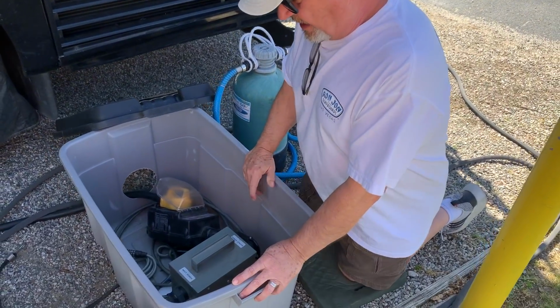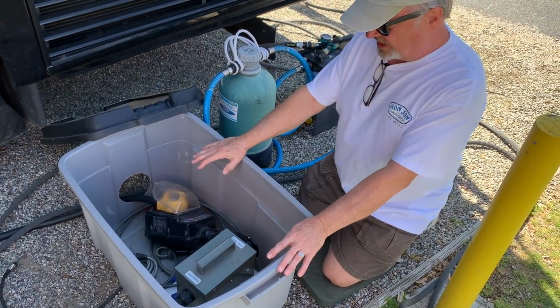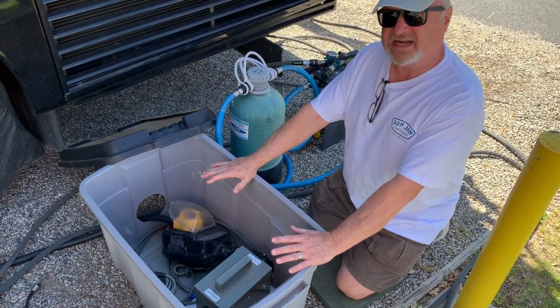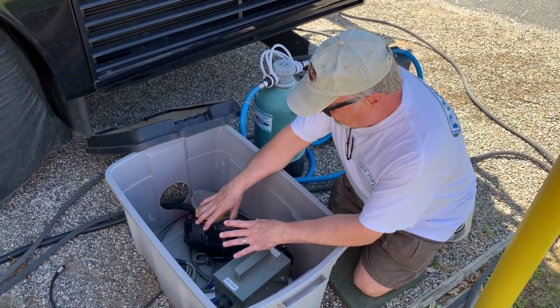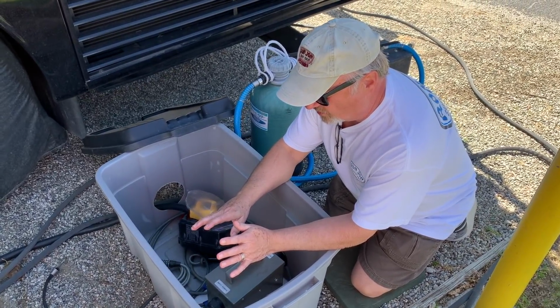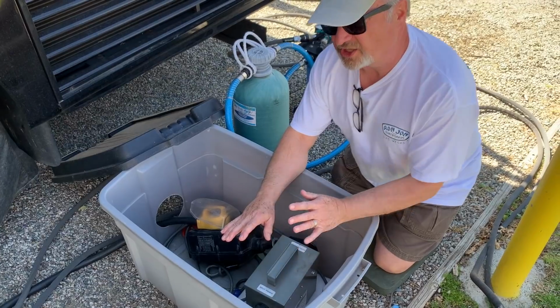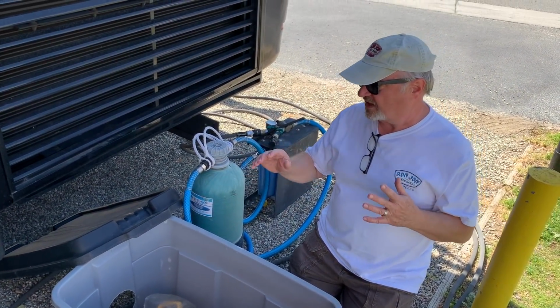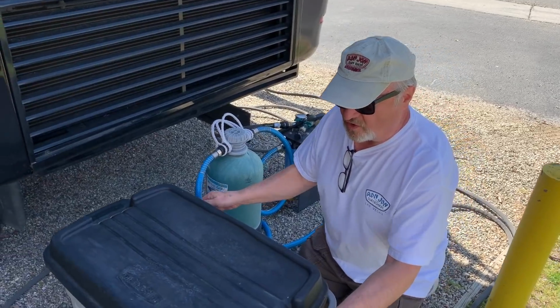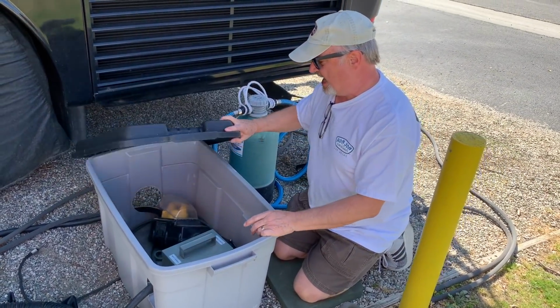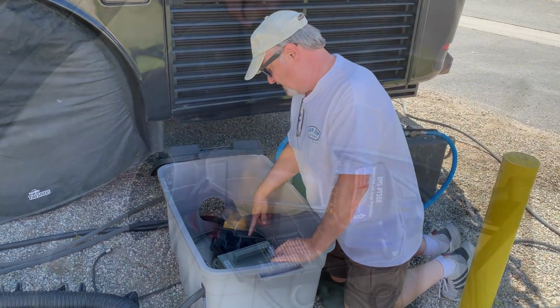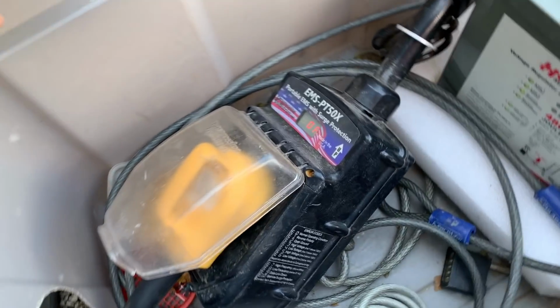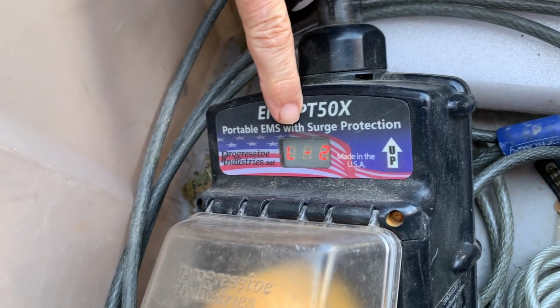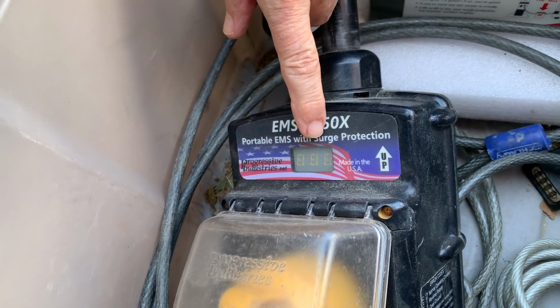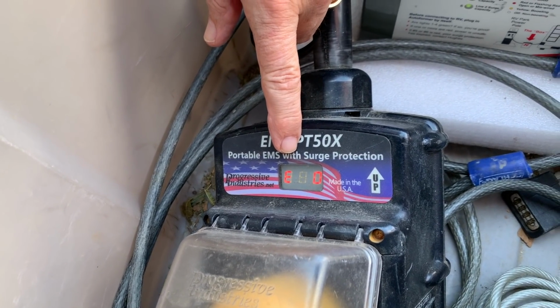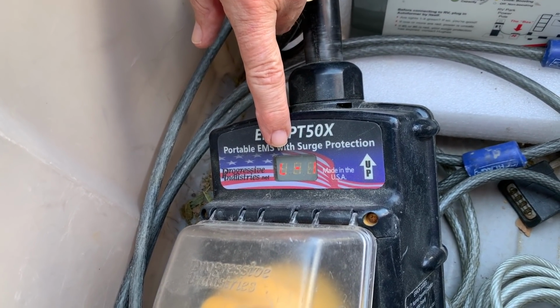Since day one I had the Progressive Industries unit, and what I didn't like was that if the power went out and I wanted to know why, I'd have to come out here, open up this box, and look at this screen. You can see Sue just turned this on, and as it scrolls through, it says Line 1 is 119 volts, 0 amp draw, 60 hertz, and E0 is what you want to see — that means no problems.